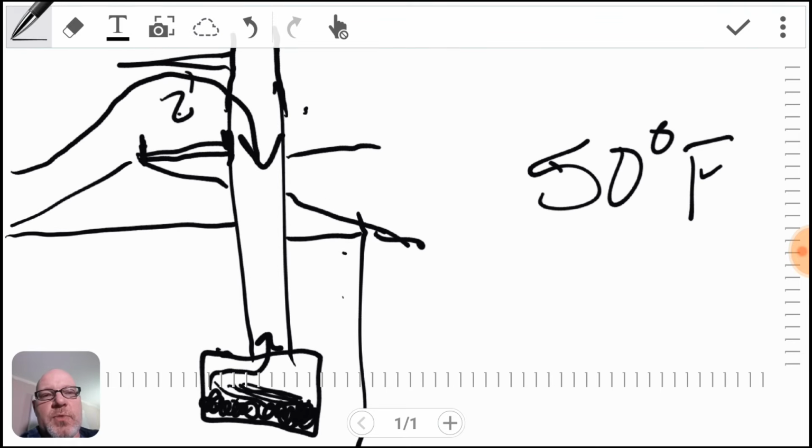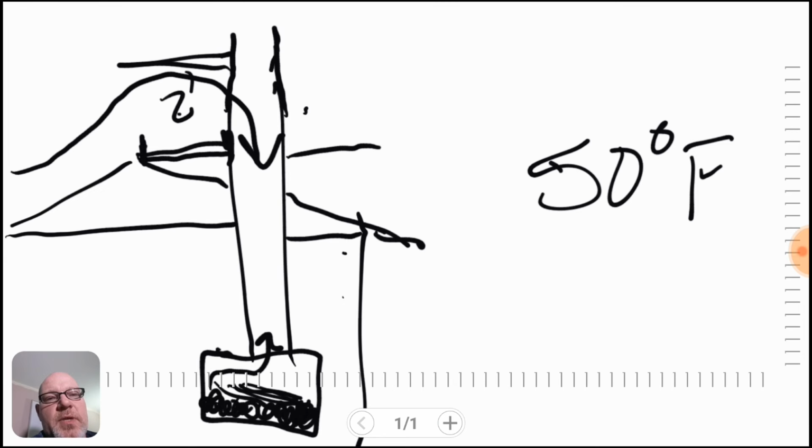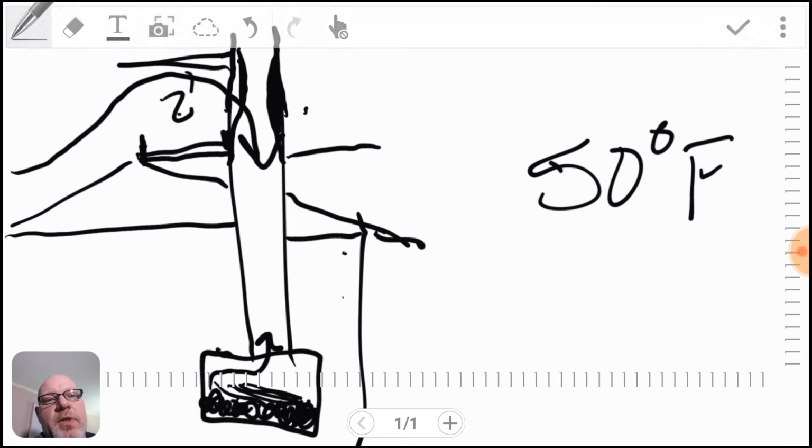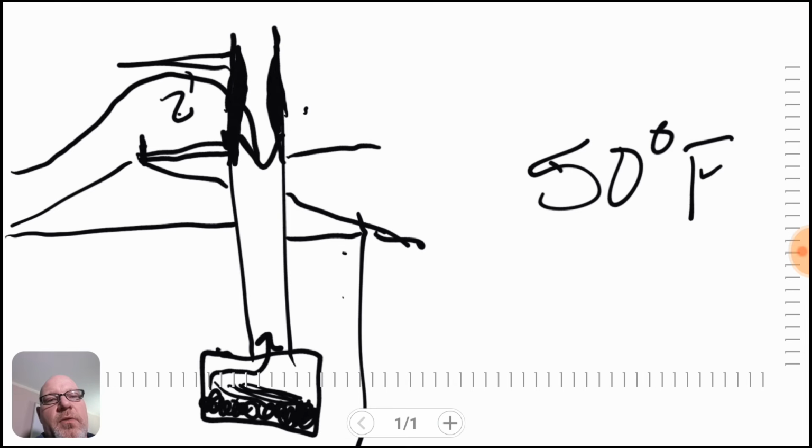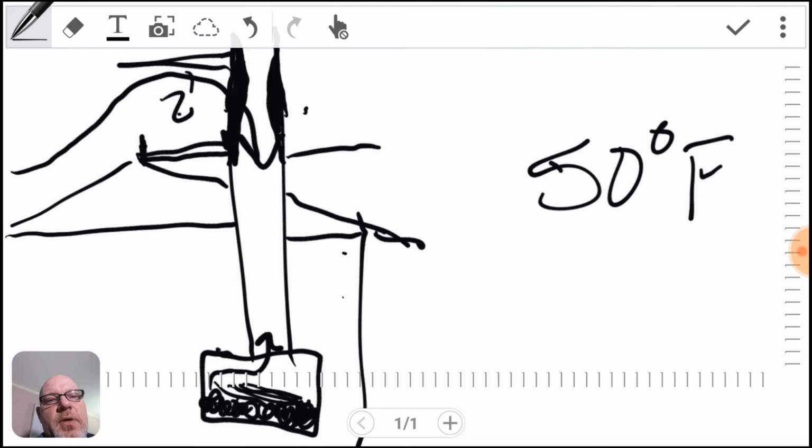It might be that you have to extend your chimney pipe up a little higher, put on another section. There are lots of other things that can cause it. Make sure you're not getting any downdrafts. Make sure your chimney cap is on there. Make sure your flue is clean, because if your chimney pipe isn't clean, creosote can start to build up, and the more creosote builds up, the more it's going to restrict the airflow. It also causes more potential for chimney fire. So make sure that's clean and the passageways are all clear.